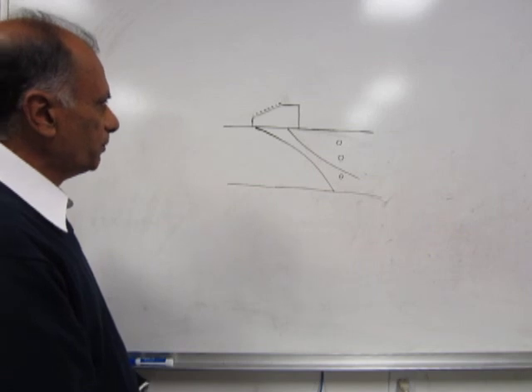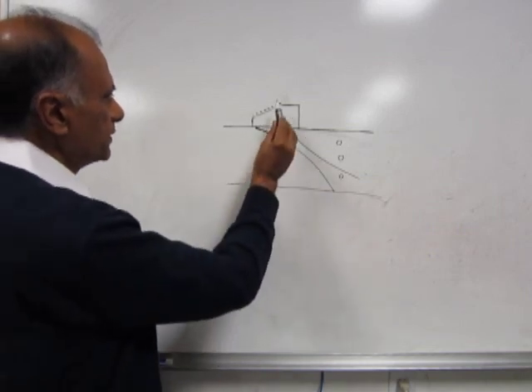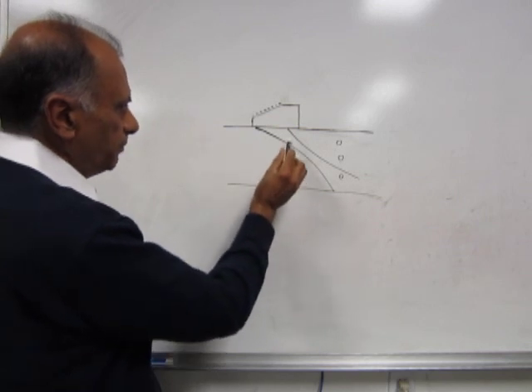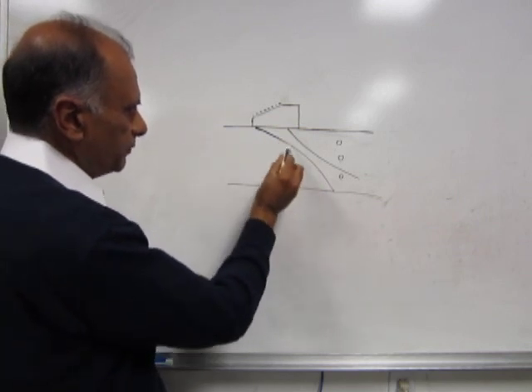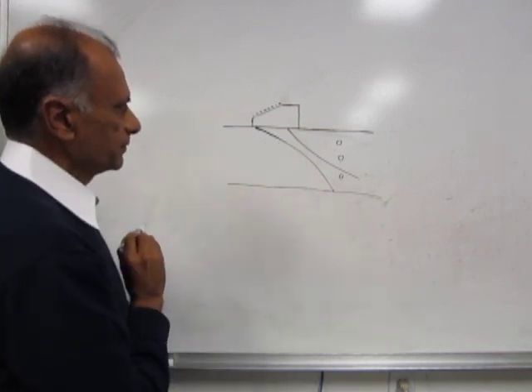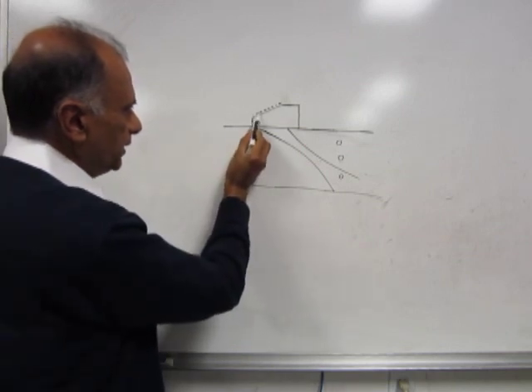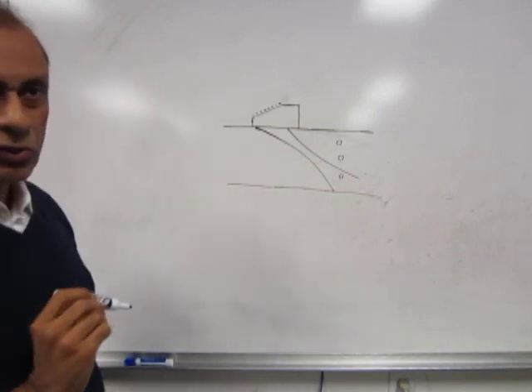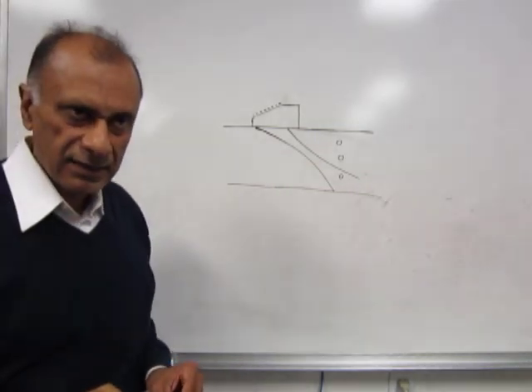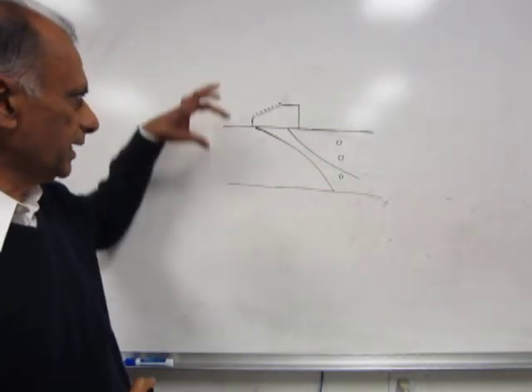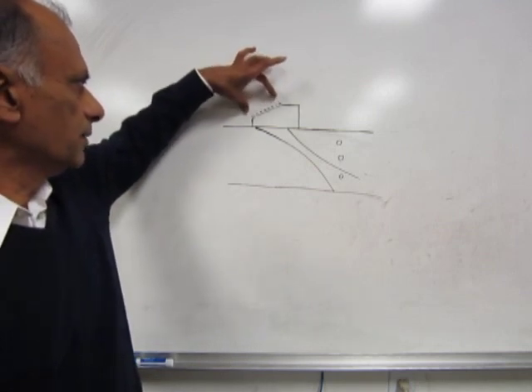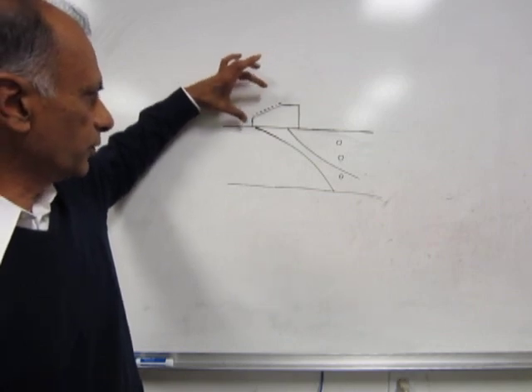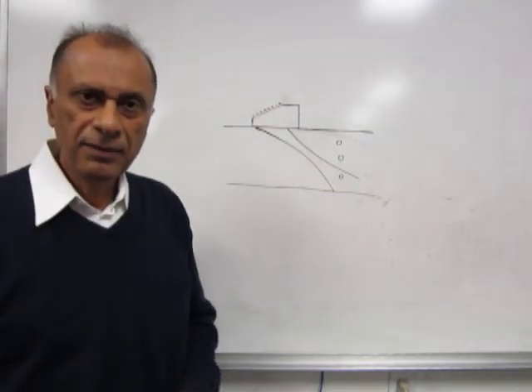But now if we pulse this crystal first and then these with a time delay, then the beam instead of going in this path it will actually go in this direction. And if we pulse this one first and then these later on, then the beam would actually go there. So what the phased array machine does is that it times these pulses going to these crystals so that we can actually control the refracted angle of the beam.